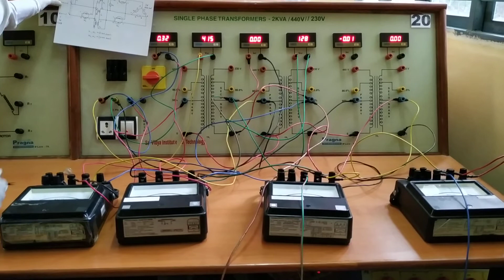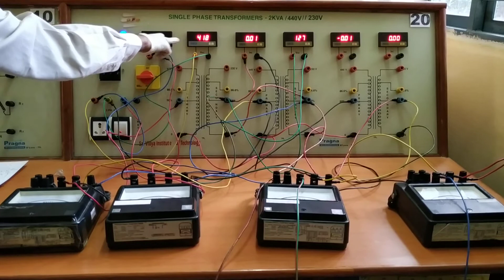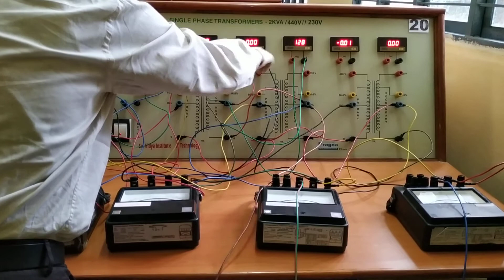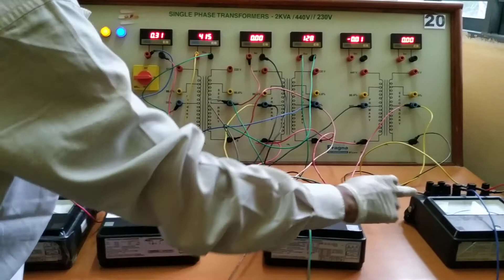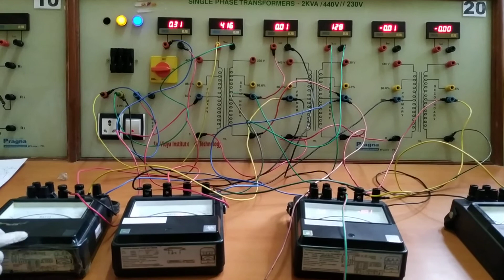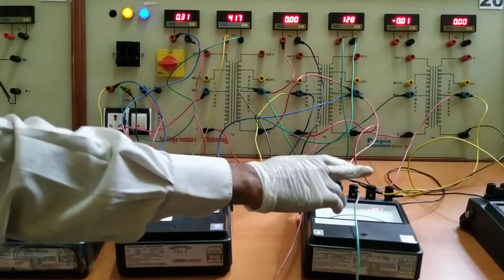Initial reading without applying the load: V1, the line voltage, is 418 volts, and current is 0.3 amperes. V2 on the secondary is 128 volts, and current is almost close to 0 amperes. Then we have W1 0, W2 150, W3 0 and W4 0.